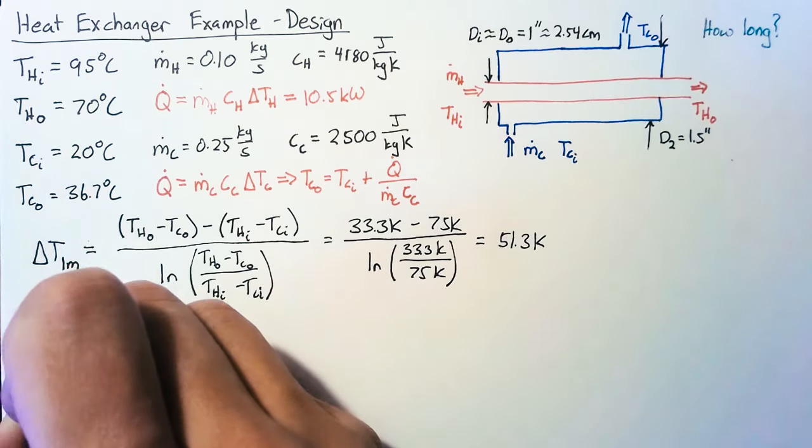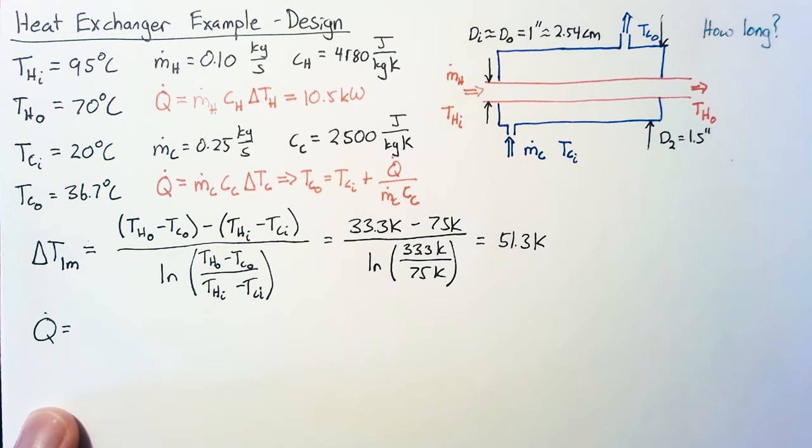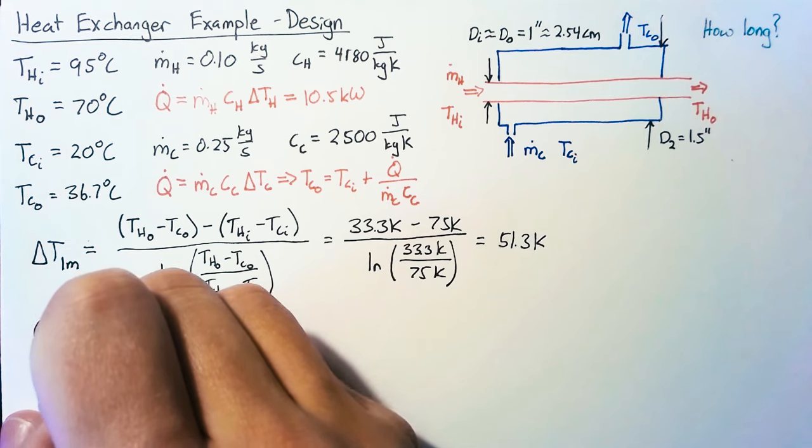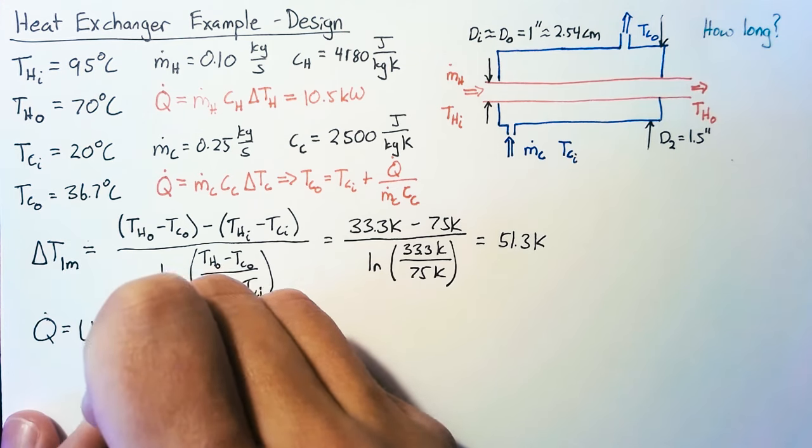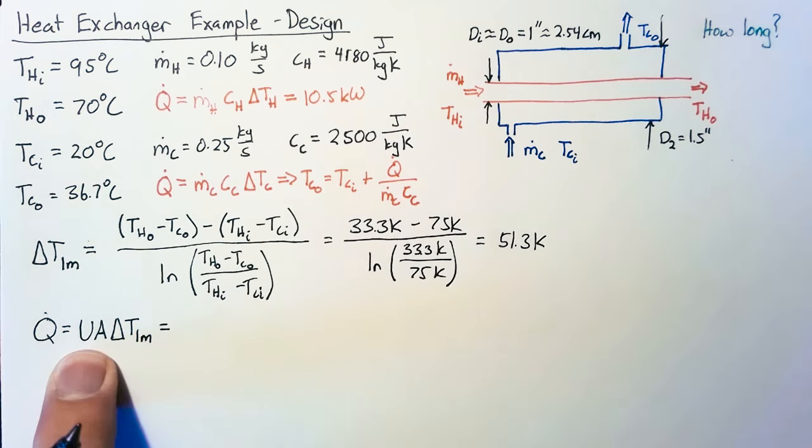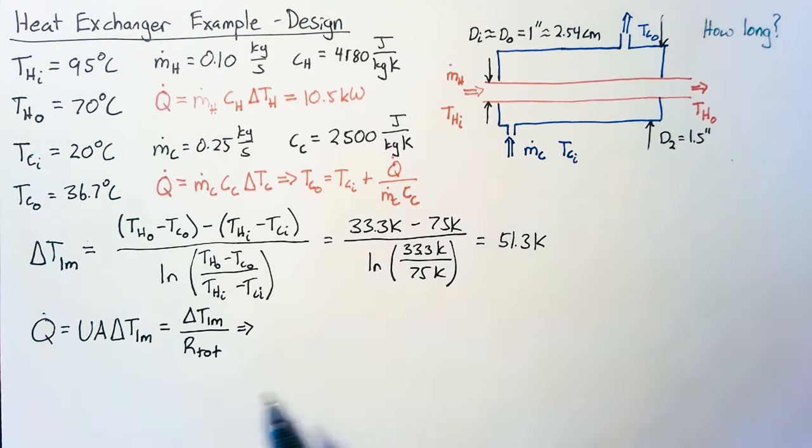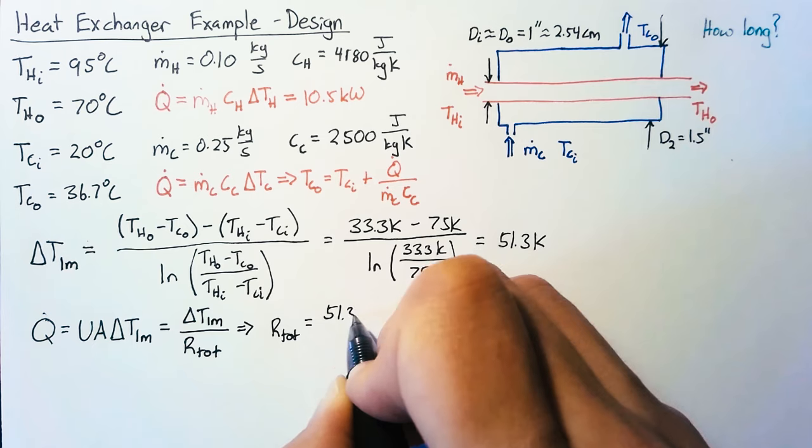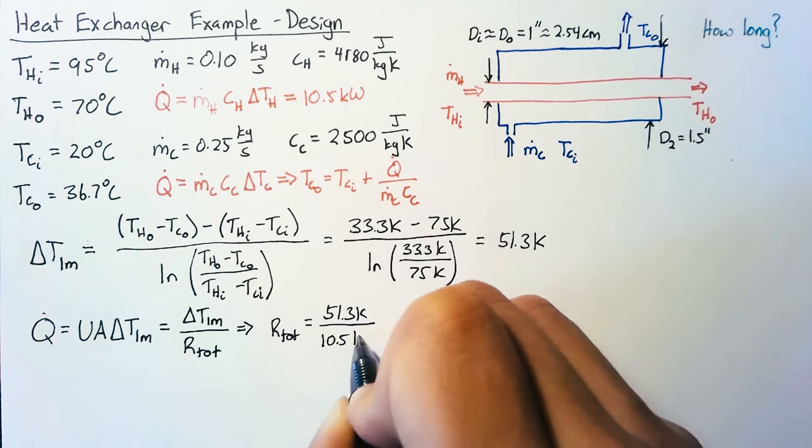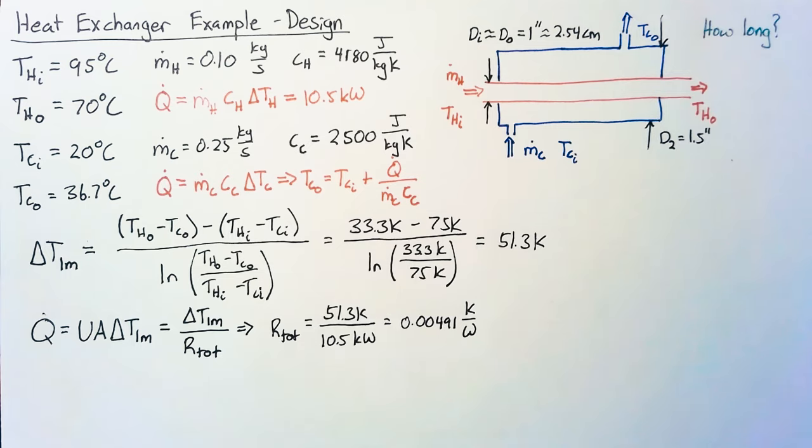With that, we can use another equation for Q_dot. This looks at the actual heat transfer based on thermal resistance between the two fluids. Q = U*A*ΔT_lm. Personally, I prefer to think in terms of thermal resistance, so this UA term is the same as one over the total thermal resistance. From that, we can solve for R_tot. It will be 51.3 Kelvin divided by that Q_dot of 10.5 kilowatts, which ends up as 0.00491 Kelvin per watt. This is a key piece in determining how long our heat exchanger needs to be.